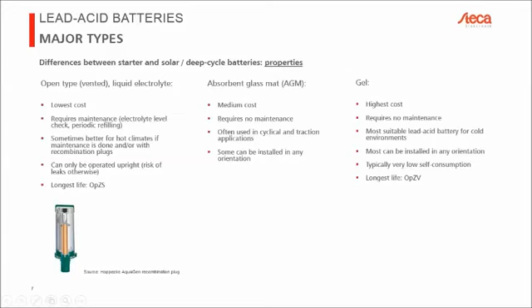Pretty much all of them can be installed in any direction, any orientation. Typically, they have a very low self-consumption, so if you leave them standing around fully charged, they will discharge a little slower than the other counterparts. Of the gel batteries, the ones with the longest life are typically the OPZV, which is almost the same thing as the OPZS - again tubular electrodes, but in this case with gel as the electrolyte.